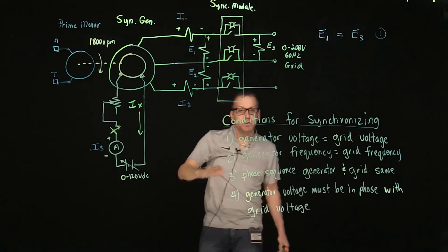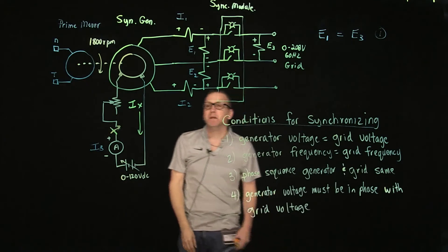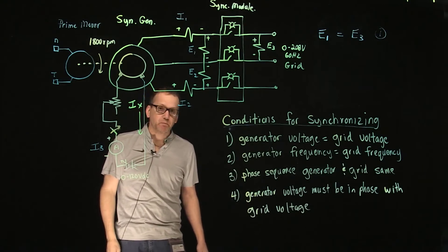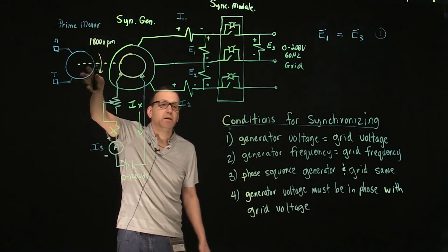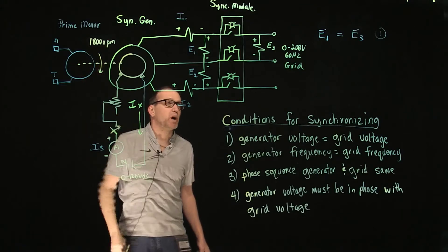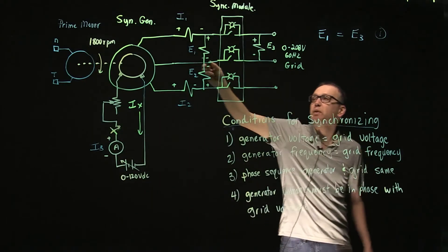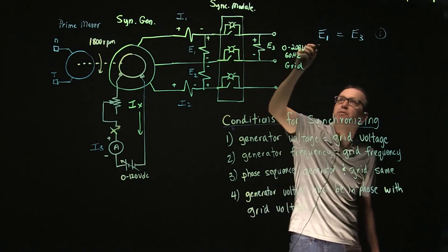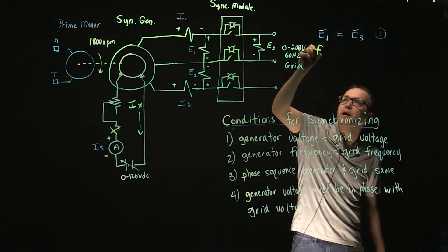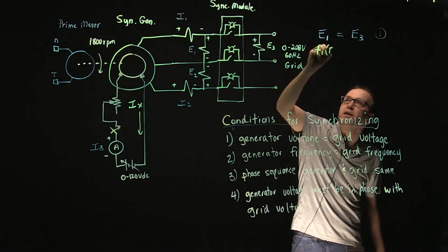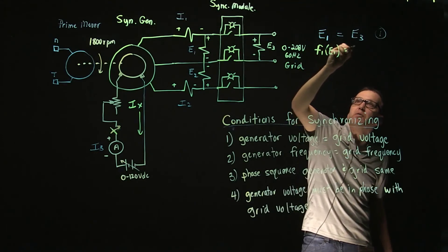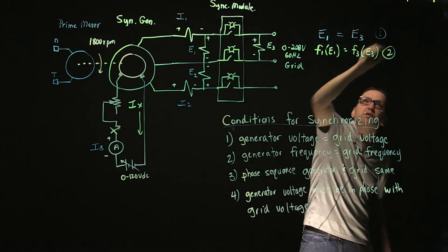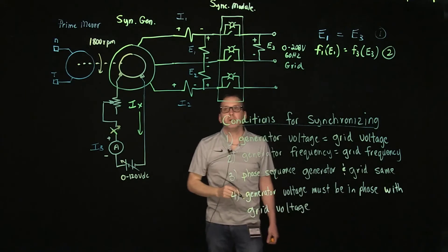For condition number two, the generator frequency must equal the grid frequency. To control the frequency of the generator output, we need to control the speed or torque on the prime mover. We are going to use meters E1 and E3, but in the LVDAM software we can also set these up as frequency meters — F1 derived from E1, and F3 derived from E3 — to determine condition number two.